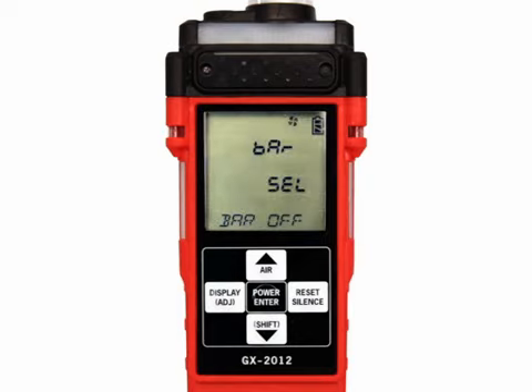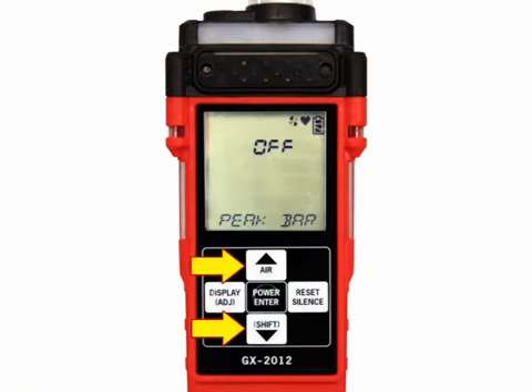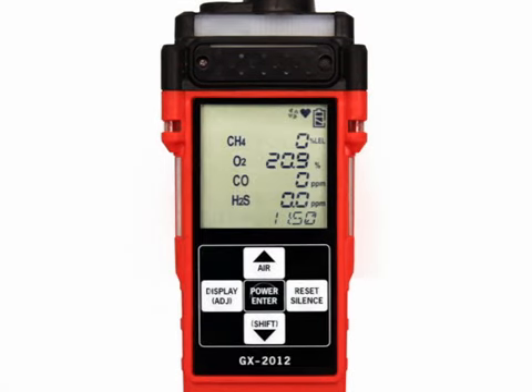The Peak Bar Select screen allows you to turn the peak bar on or off. The peak bar appears along the left side of the screen during normal operation and on the peak screen in display mode. It shows the peak readings for each channel in bar graph format. To adjust the peak bar selection, press and release the Power Enter button. Use the Air and Shift buttons to make your selection and press and release the Power Enter button. Press and release the Display Adjust button again to return to normal operation.